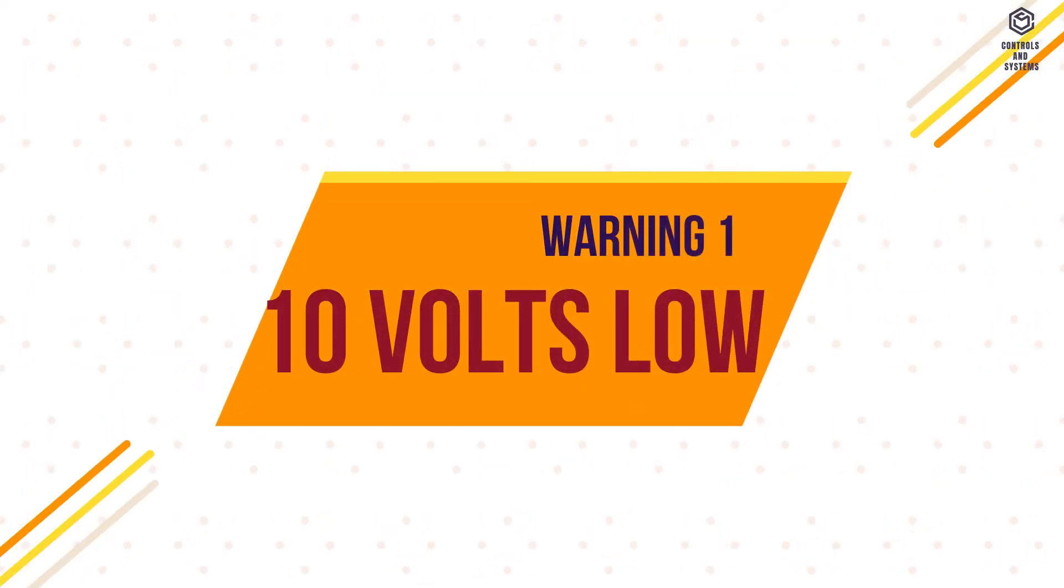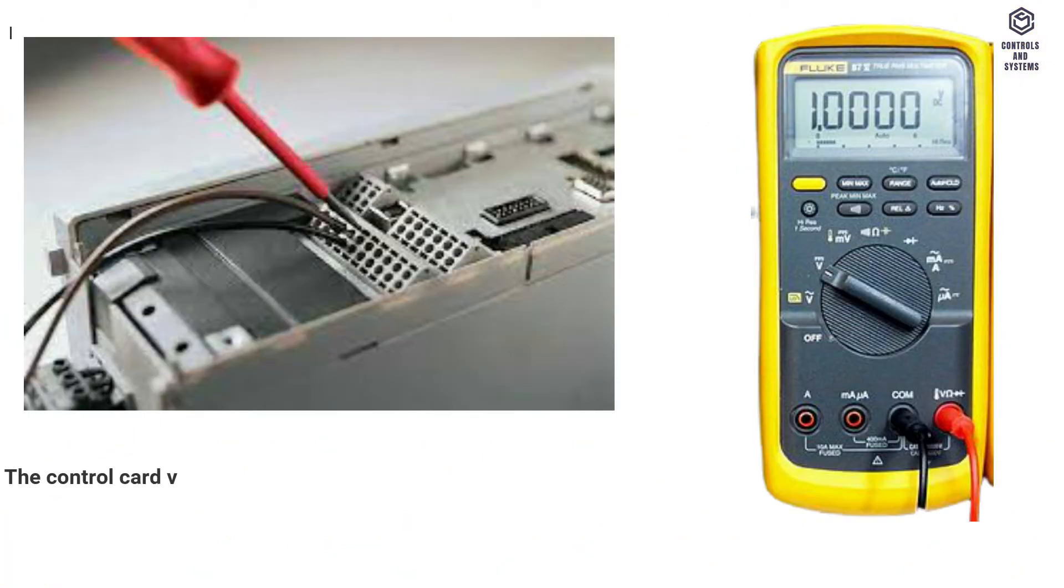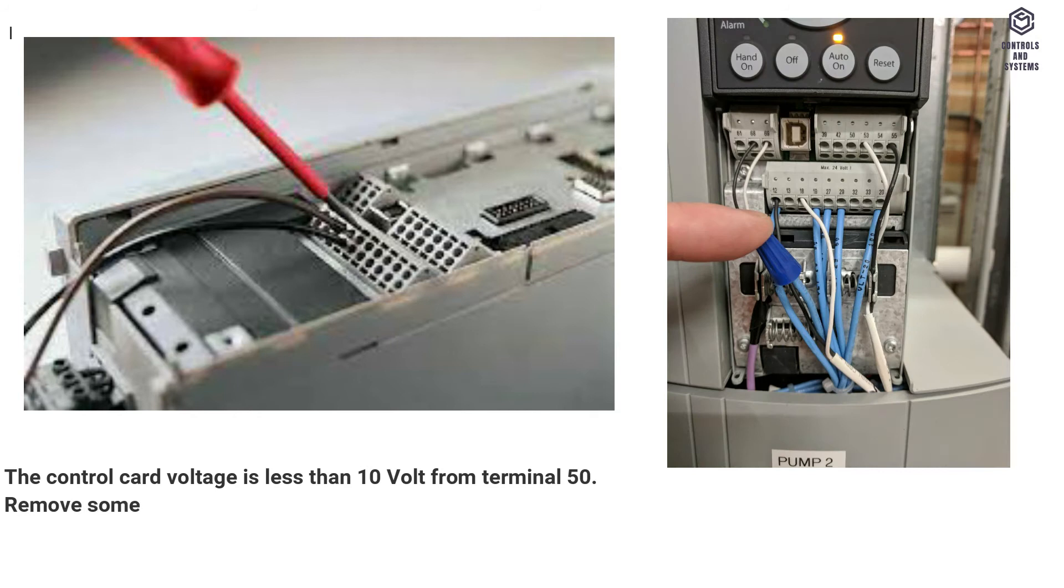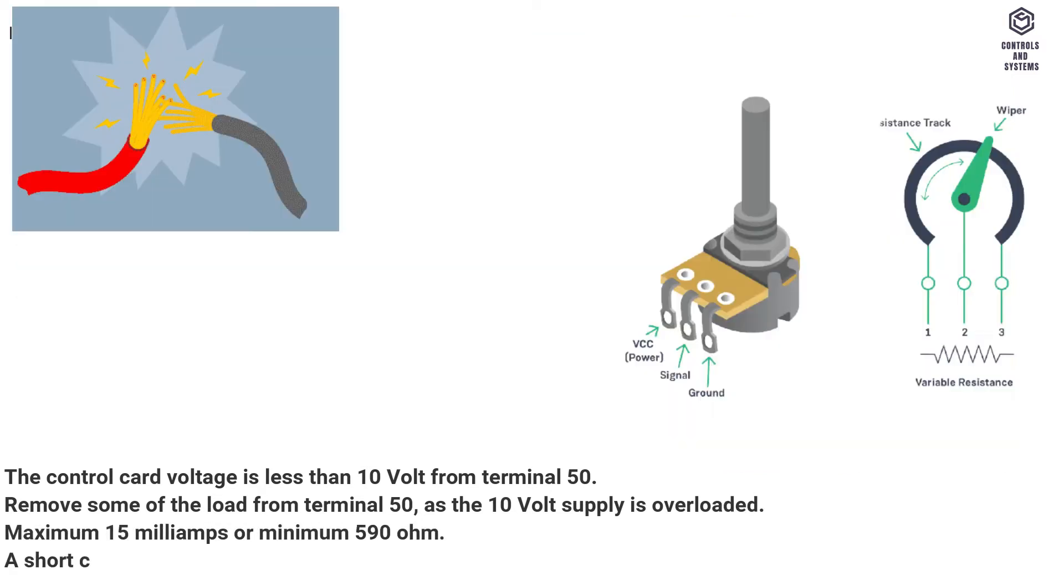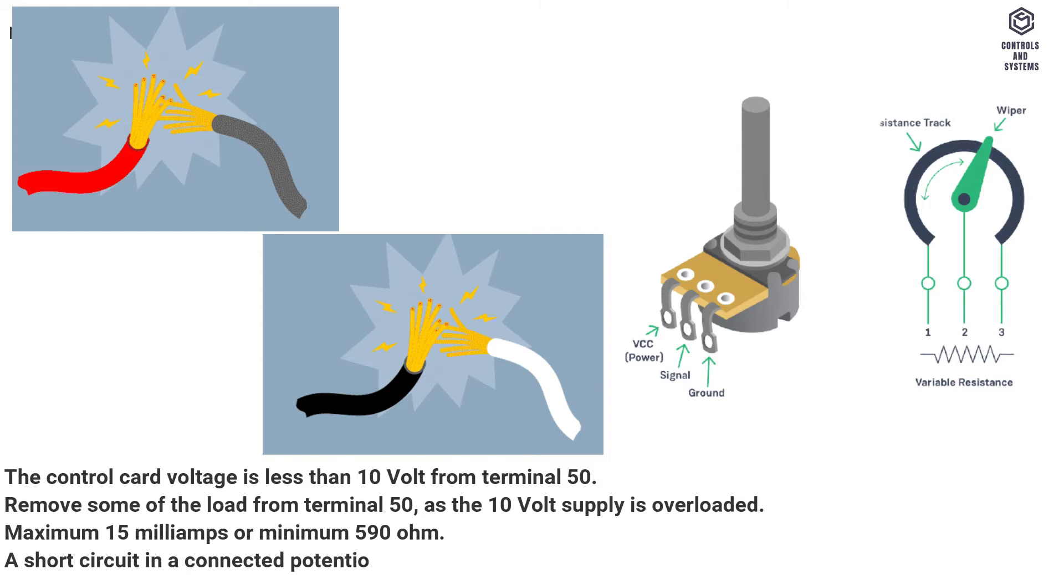Warning 1, 10V low. The control card voltage is less than 10V from Terminal 50. Remove some of the load from Terminal 50, as the 10V supply is overloaded. Maximum 15mA or minimum 590Ω. A short circuit in a connected potentiometer or incorrect wiring of the potentiometer can cause this condition.